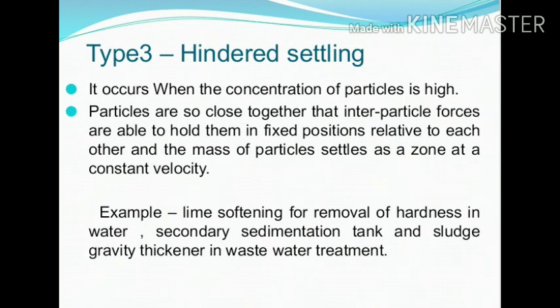Type 3 is hindered settling. It occurs when the concentration of particles in the turbid water is high. The particles maintain their relative positions with respect to each other due to inter-particle forces which hold them in fixed positions. Examples include lime softening for removal of hardness in water, secondary sedimentation tanks, and sludge gravity thickeners in wastewater treatment. The concentration of particles increases from top to bottom, leading to thickening of sludge.